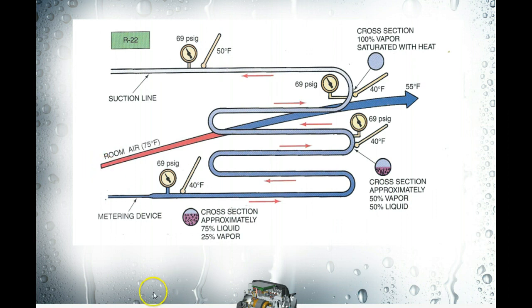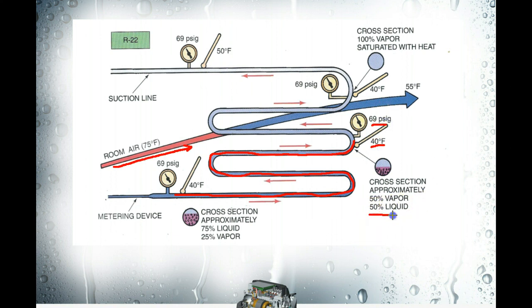Here we have 75 degree Fahrenheit room air being blown across the evaporator coil. This refrigerant is flowing through here, boiling and absorbing heat as it changes state. Remember, that change of state takes a tremendous amount of heat energy — it's absorbing heat just like a sponge. Theoretically, halfway through the coil, we're still at 40 degrees and 69 PSI G, and we're now 50-50 liquid and vapor. Because we have liquid and vapor together, we are still in the saturated state, and we continue to boil all the way through this coil, absorbing heat along the way.